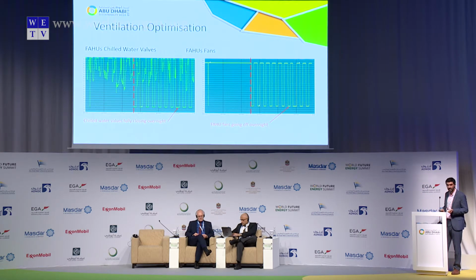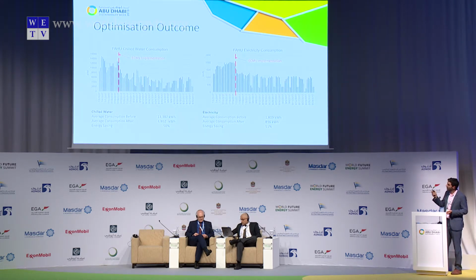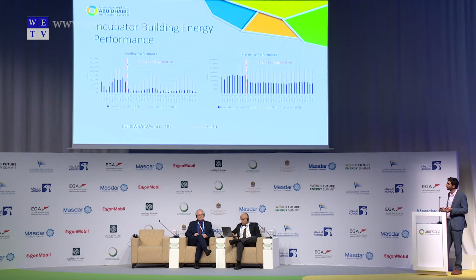So this was a simple thing we did and it saved us. I'll show you later on how much it saved. Since we implemented this measure, on the left side, we saved about 58% on the chilled water consumption. And on the electrical fan energy, we saved about 51%. That is equivalent to almost 100,000 dirham for the whole year. So that simple measure made a big change. And I can tell you that in many buildings, ventilation systems are running 24 hours, 7 days a week. So these simple measures can save a lot of energy and money, and eventually reduce the gap.